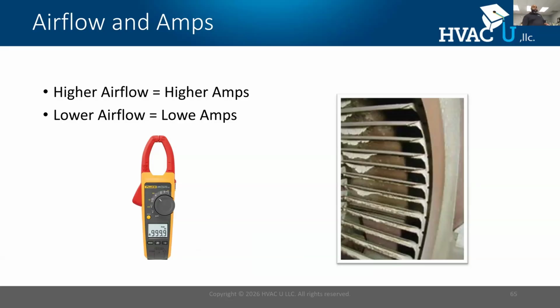Won't spend a ton of time on electrical, but you can also identify some airflow issues by measuring amps. If I have low amp draw compared to what the motor says, if you're qualified to take the electrical readings, that's also an indication that you may have something. So this is another measurement that can be taken to help you pinpoint exactly what's going on.